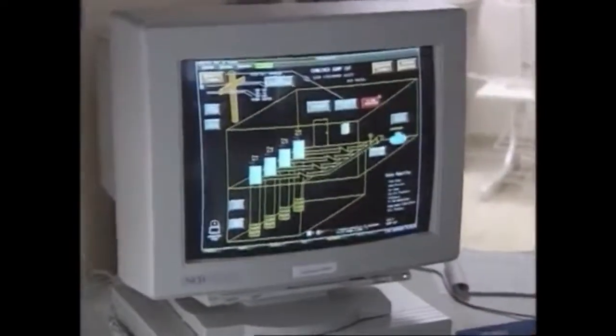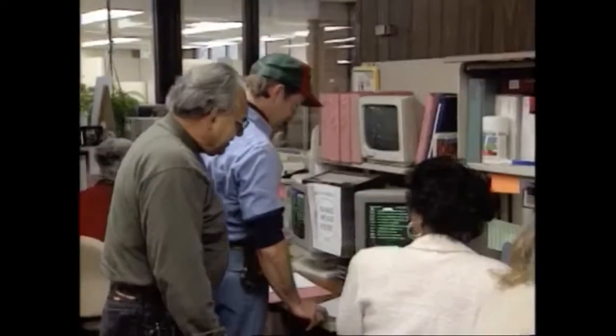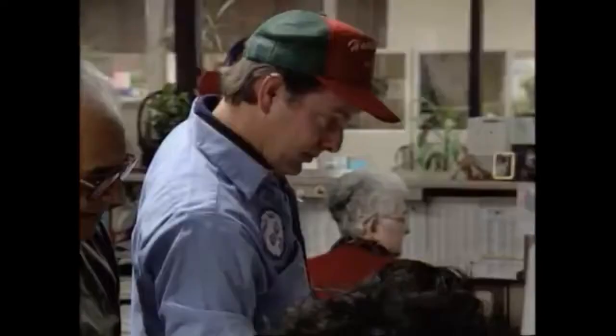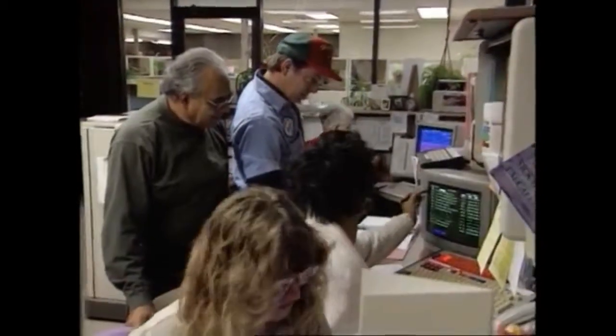Generally, the graphic information available to the dispatcher when a lift station alarm occurs includes lift station number, flow meter number, time, date, alarm acknowledge indicator, power failure, transmission line failure, station power failure, standby generator running, high wet well, high dry well, pump 1 failure or pump 2 failure, and site security. Additional information that can be pulled up on the station are critical utility phone numbers, who's on standby, daily log entries, comments that may have been put in there by an operator earlier in the week. He may have had a problem. Operator response and action taken by the dispatcher.